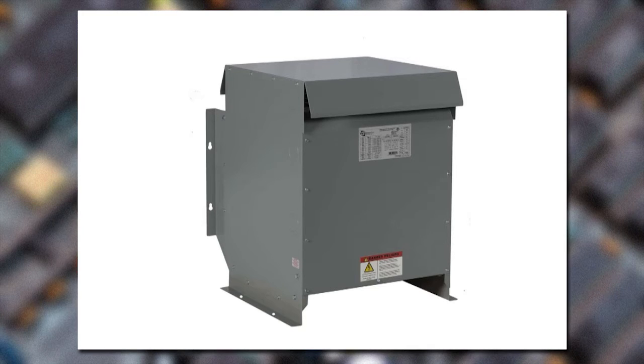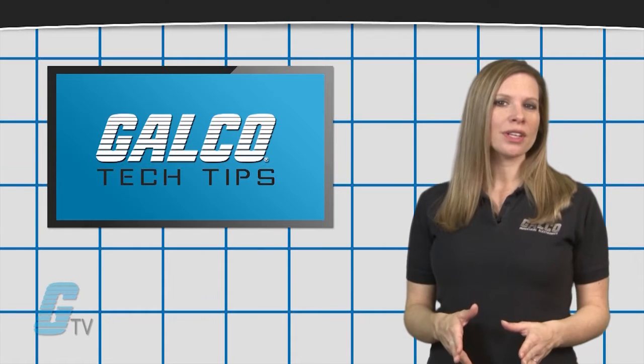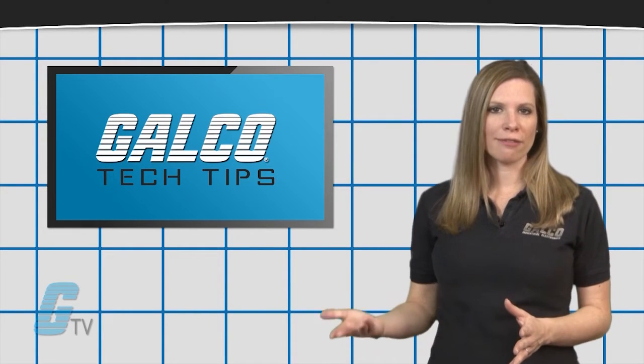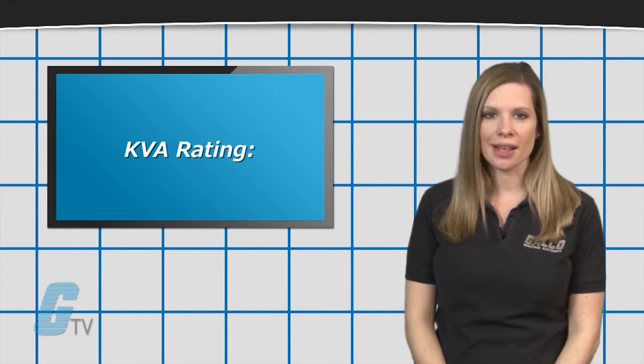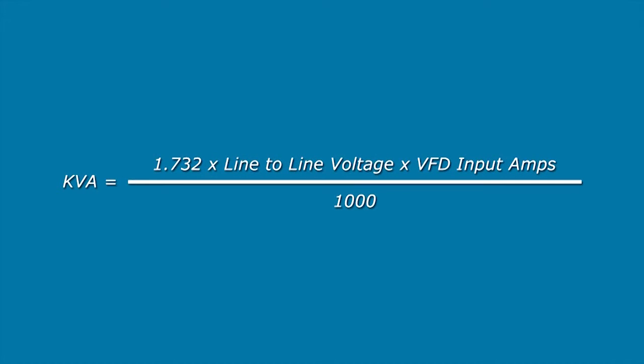from other sensitive electronic equipment. If your electrical system requires a drive transformer, you will need to calculate the KVA rating. This is done by multiplying the line to line voltage with the VFD input amps and 1.732. Then divide this number by 1000.